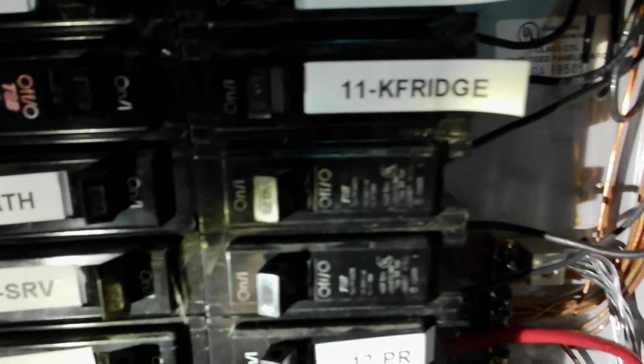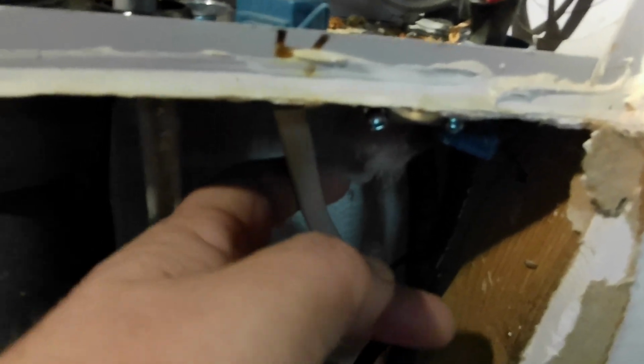Now, what will end up happening is some of these circuits, I'll take them off the breaker and put these little Wago connectors, and run another number 14 wire, which is this white wire right here. I'll end up running that back to the other panel in the room you'll see here in a moment, and those will be my critical loads that I want to be able to run off of solar.